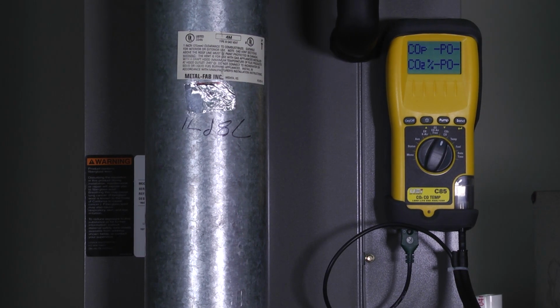And carbon is a bad thing, especially when we talk about a condensing furnace where you have carbon and water come together. They can create carbonic acid, which can rot out a heat exchanger. But even on an 80% efficient furnace like this, we can actually cause carbon to start building up inside. And the great thing about carbon is that it's an insulator, so we're not going to get proper heat transfer on our systems. So when I take a look at this system, I may not be able to see from the outside that there's carbon built up inside of it.